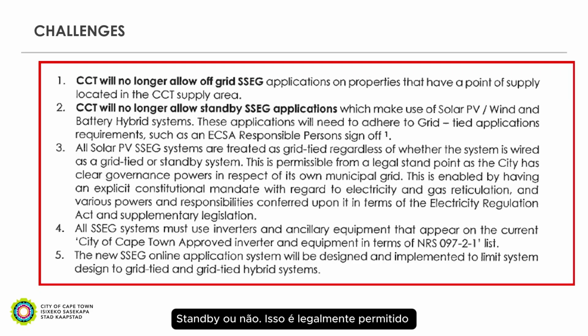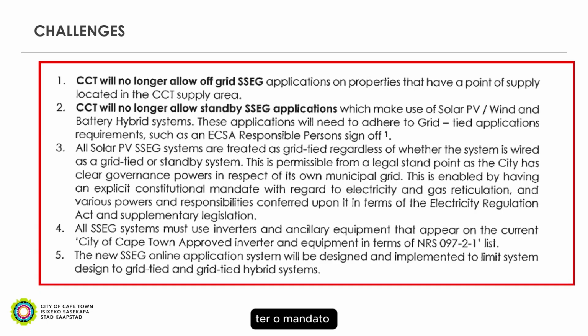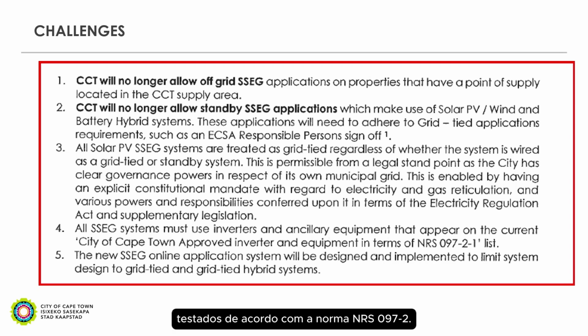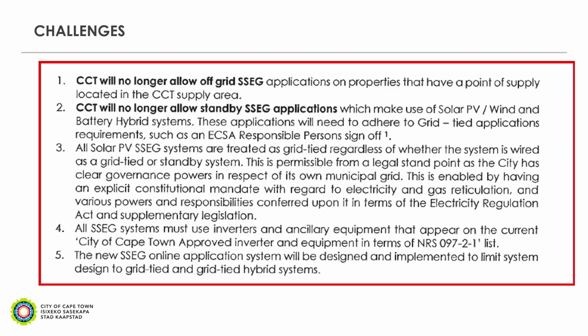And that's permissible from a legal standpoint, as the city has clear governance powers in respect of its own municipal grid. This enables us to have the mandate with regards to electricity, gas, and reticulation, and the various powers that are conferred to us as part of the ERA, the Electricity Regulations Act. And then obviously all SSEG systems must use the approved inverters that have been tested according to the NRS 097-2-1 list, which we published on our website. And then the new SSEG online system, which we have designed around these simplified rules and with the approved inverters.